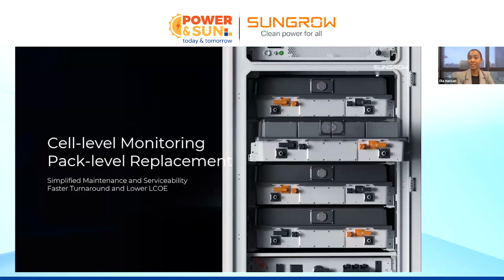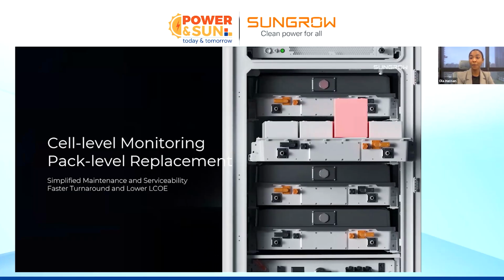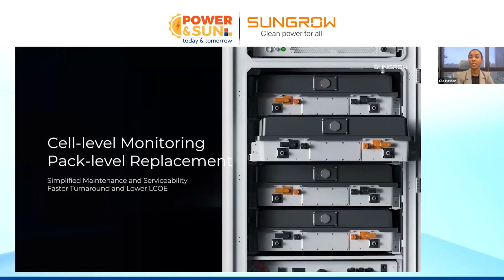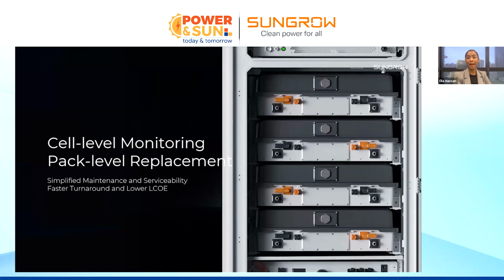As I mentioned, we have the cell level monitoring and the pack level replacement, which is very helpful, especially in the operation and maintenance. So if a battery pack or a battery rack fails, the other battery racks will continue to operate individually, independently. They will not affect each other. So each battery rack is isolated from the other one, and we can easily replace this battery rack with a new one. So we have simplified maintenance and serviceability as well, giving you lower LCOE and also OPEX cost as well.